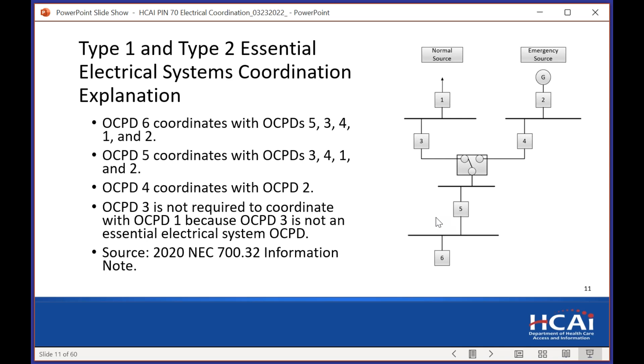The source of this figure on the right is from the 2020 National Electrical Code, 700.32. So the right type of breaker is important. We have two examples. The one on the left has a 400 amp thermomagnetic breaker. You're seeing that we have overlap here between the upstream breakers and this 400 amp breaker. When we replace that 400 amp with an electronic trip unit, we get this system to coordinate. So you can see that in your plans, you need to specify the right type of breaker during plan design. And this is why we're asking for proof of coordination during plan review.